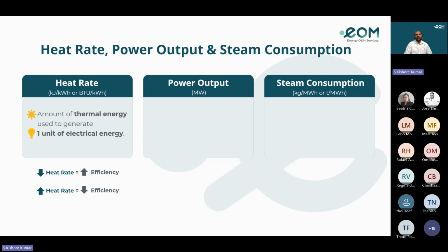So why does it matter? A lower heat rate saves fuel and money. A higher heat rate means the turbine is not running efficiently, maybe due to maintenance issues, old design, or poor steam conditions. So our goal is always to lower the heat rate to improve the efficiency.